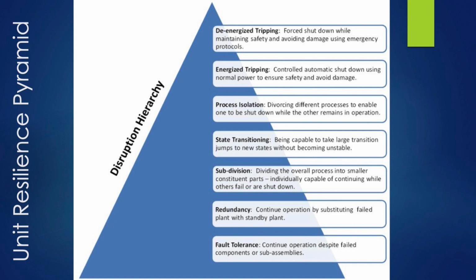Energized tripping, islanding capability, is a capability where you step down the entire unit, lock stock and barrel, from the grid. You separate from the grid so that all the nonsense and disturbance that happens there doesn't affect you any further. But it is technically complicated and risky to do, and not simple. You need very good control systems and so on.